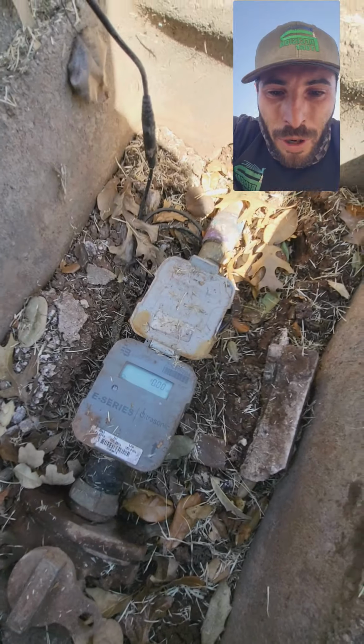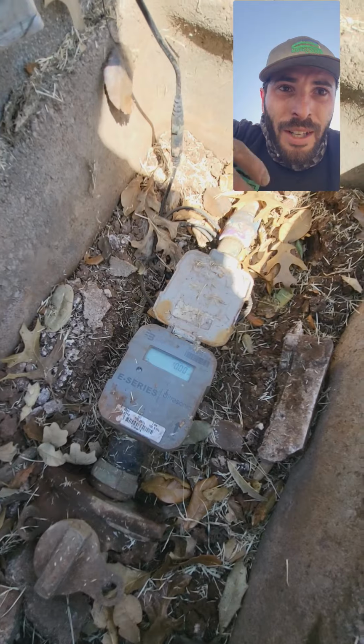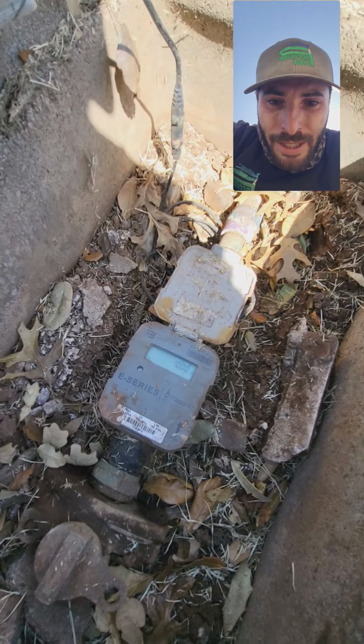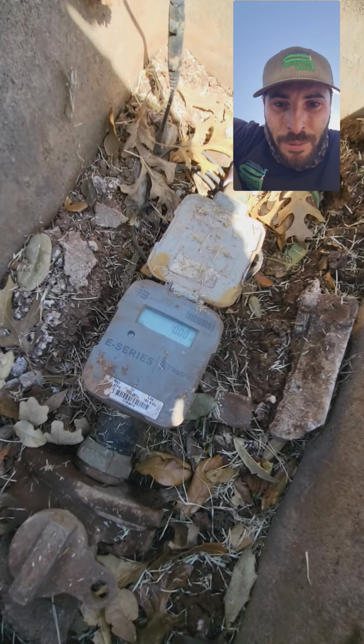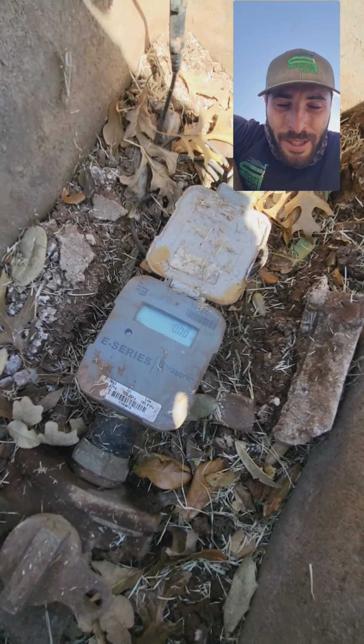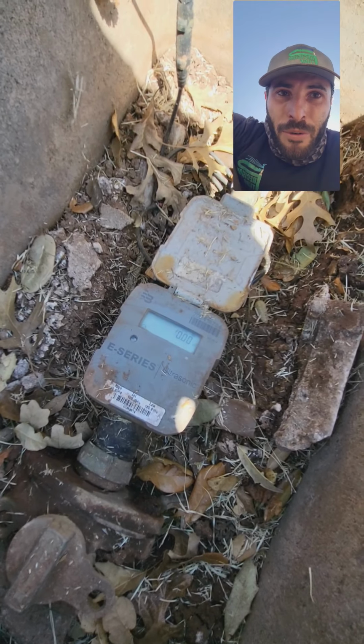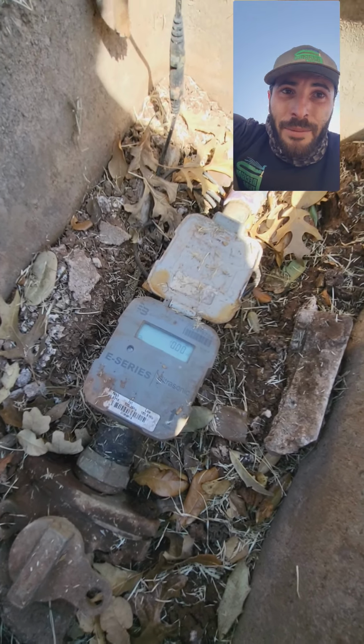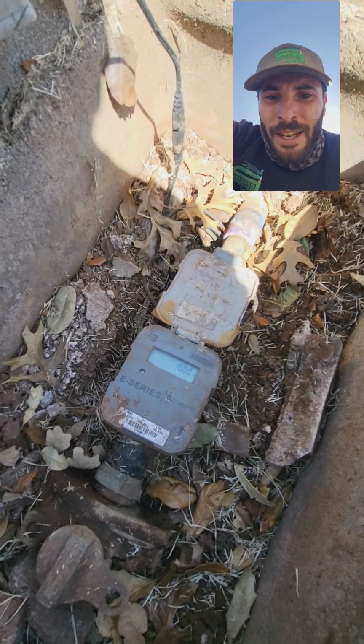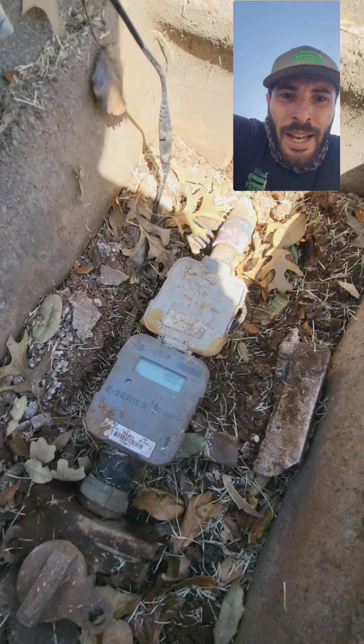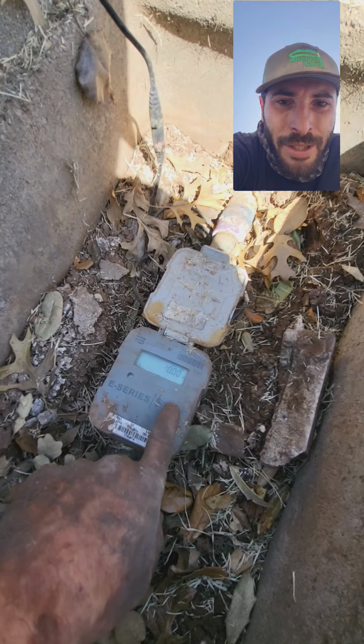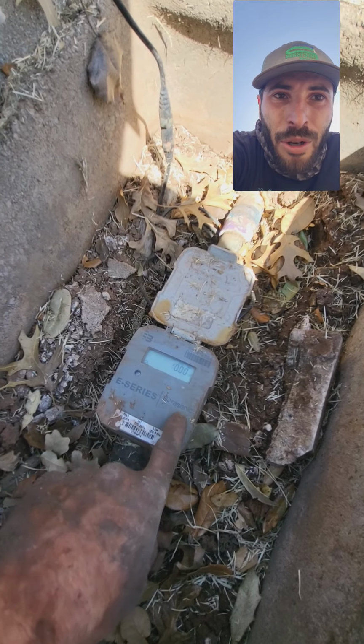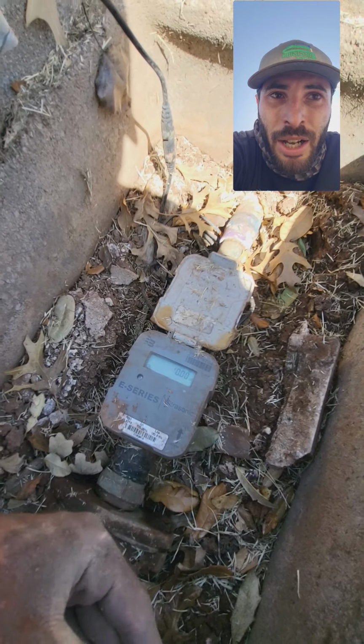So always do your work, always double check. And that's it. It's really simple. Just double check the water meter, check the water rate. If it says 0.00, you know that you don't have an issue with the sprinkler system. If you have a sprinkler head that is just trickling with water and the water rate is saying 0.00, then that is just the low head. So that is just water pressure.